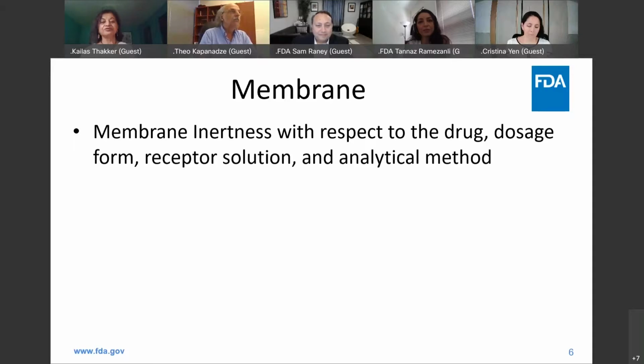Then I might want to point out that when Christina was giving her presentation, she had mentioned that initially what we look at is the physical integrity. Do not forget the physical integrity of the membrane because we use hydroalcoholic solvents often in the industry, and some of these, they curl up.